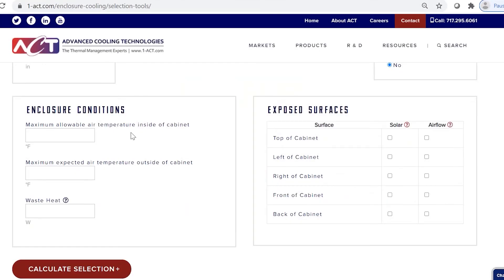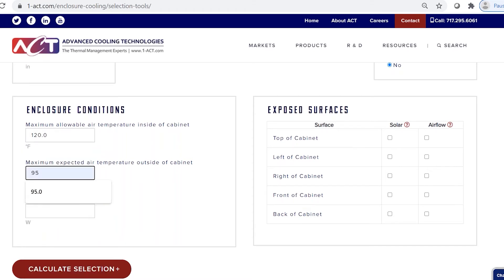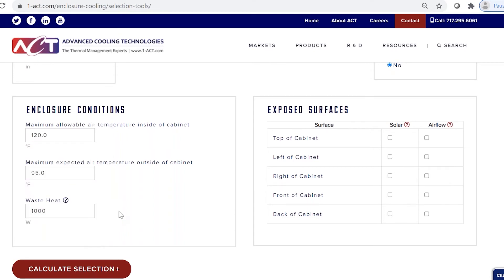Finally there are the enclosure cooler conditions. The maximum allowable air temperature inside the cabinet is 120 degrees Fahrenheit, the maximum expected air temperature outside is 95 degrees Fahrenheit, and the waste heat is 1000 watts. The final box runs calculations to determine how much additional or less heat you need to remove with your enclosure cooler, based on solar and airflow conditions.